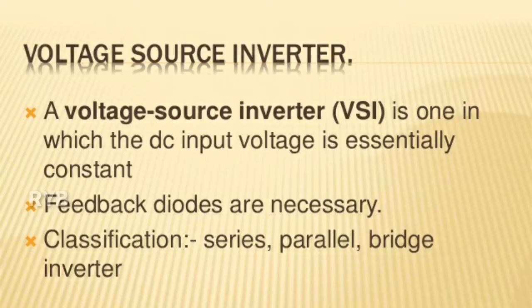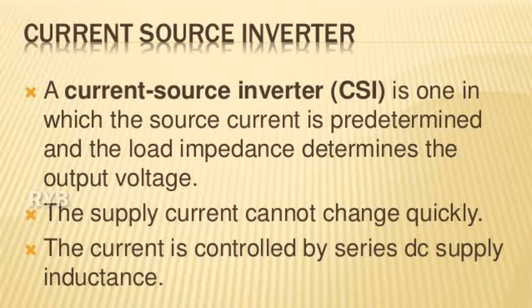Inverters are broadly classified into two types: voltage source inverters (VSI) and current source inverters (CSI). When the DC voltage remains constant it is called a voltage source inverter or voltage fed inverter. Sometimes the DC input voltage to the inverter is controlled to adjust the output; such inverters are called variable DC link inverters.